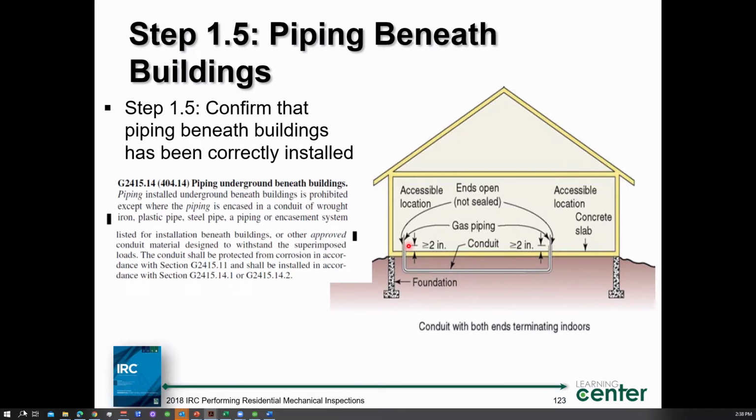Yeah, well, I think it's a pretty safe situation. It's been around since, I believe, 2012. This was put in something around there. And I think it's a good feature because if we sealed these up, we would have a gas leak that would be contained in the conduit. Eventually, if you didn't have it sealed up too well, it would tend to leak out. I'd rather know about it sooner than later. The chemical additive in natural gas is called mercaptan, right? Yeah. So that gives it that distinct odor that we know so well, that, hey, something's going on.